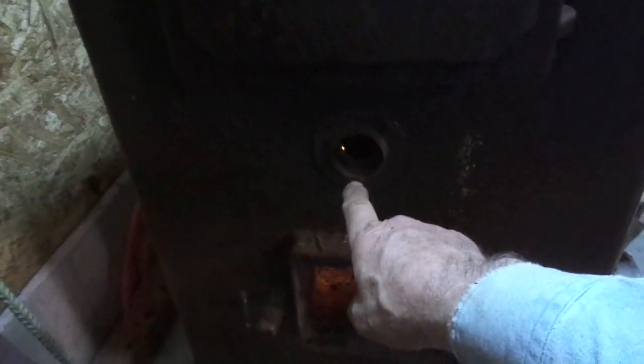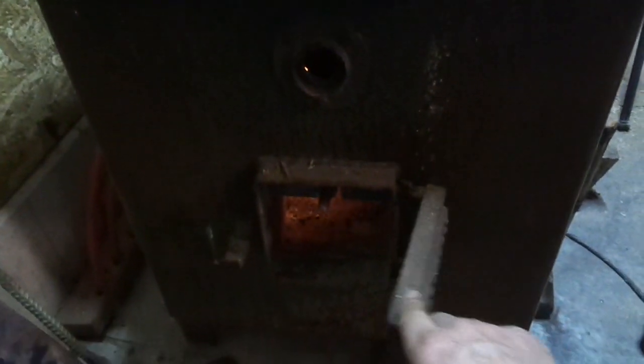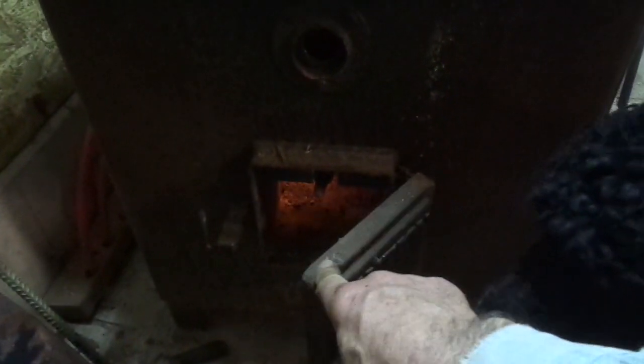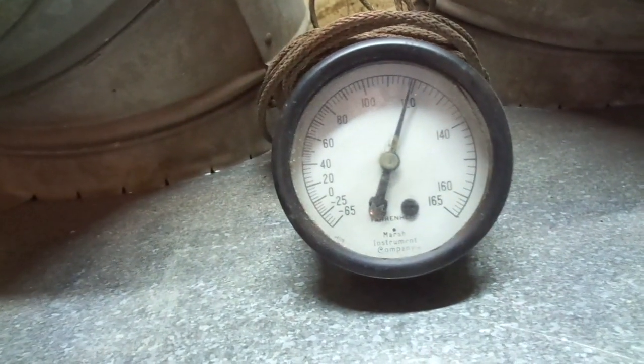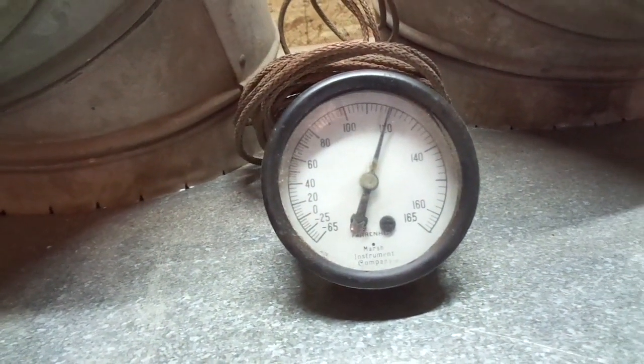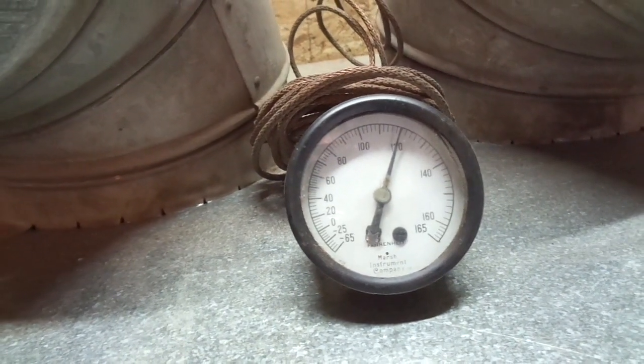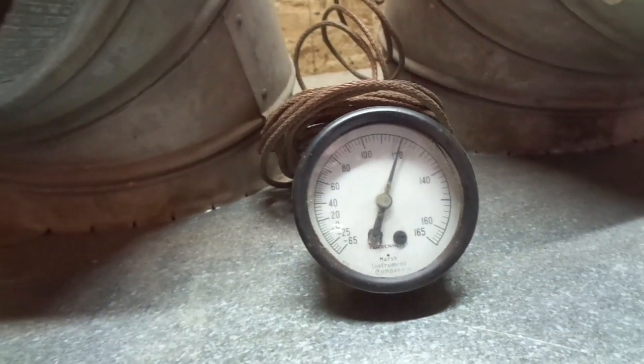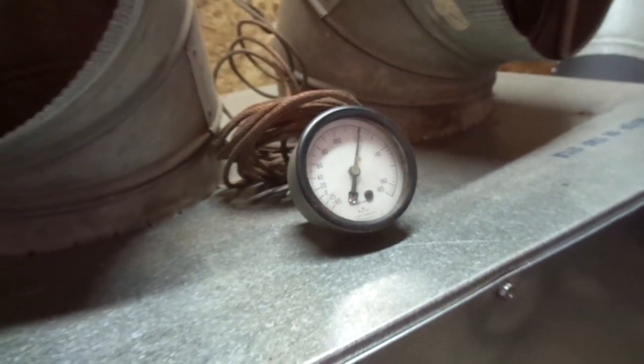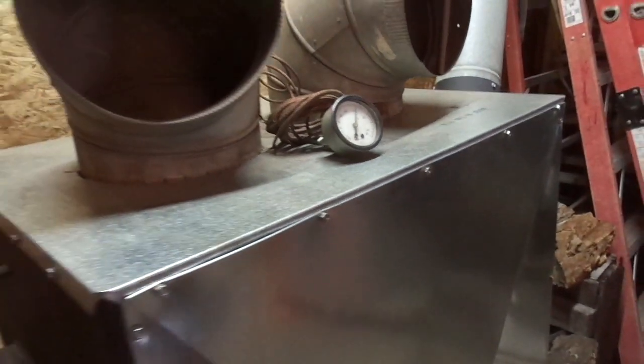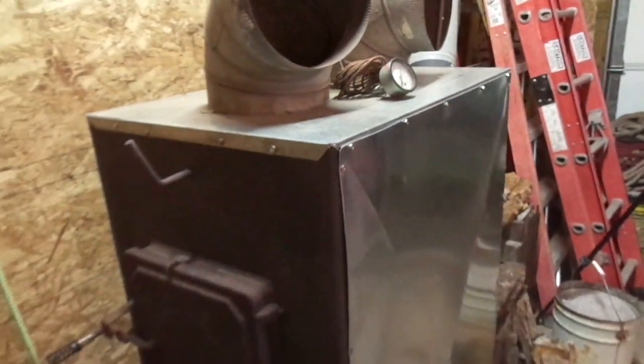I've got the ash door currently open right now because I don't have a combustion air fan yet, but I can modulate the temperature that I want very easily by adjusting this door, actually closing it or cracking it. And take a look at our discharge air temperature. Right now we're sitting at about 118 degrees. If I leave that door open for about another 10 or 12 minutes, it'll be approaching 135, 138. And that is definitely some heat coming into the space.